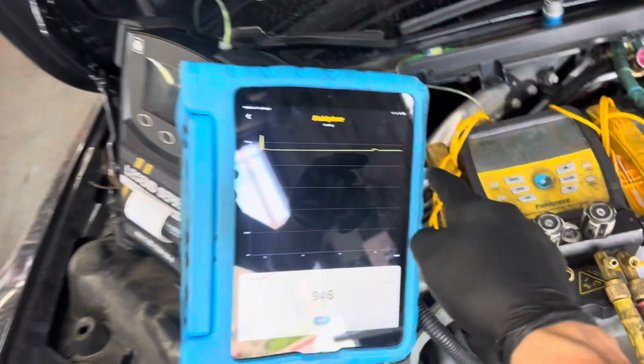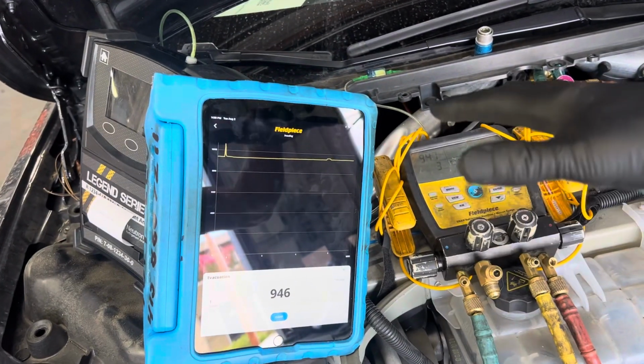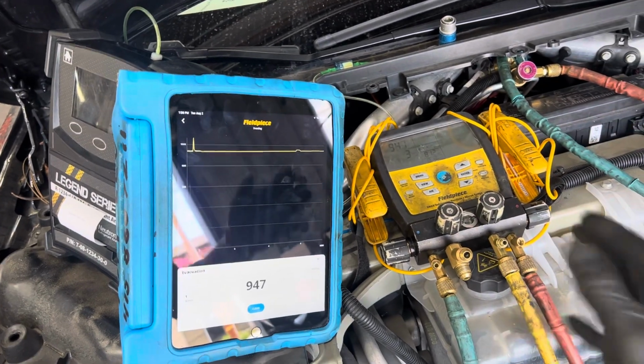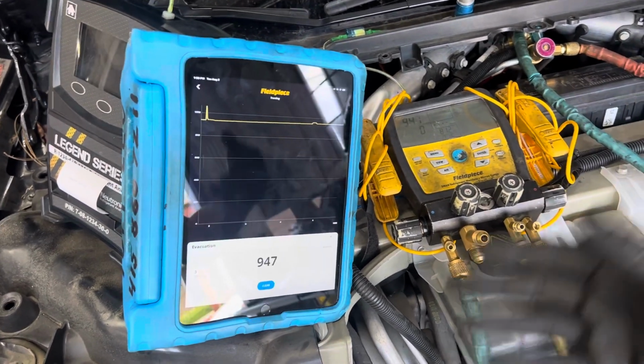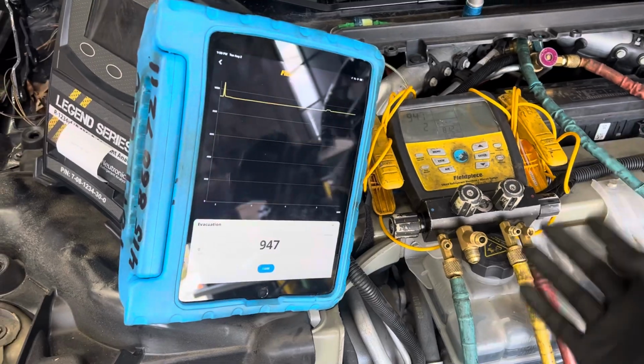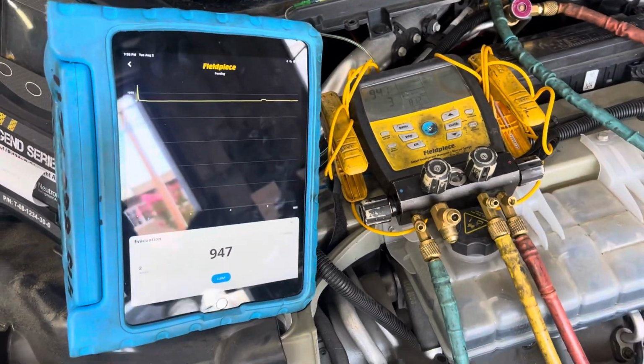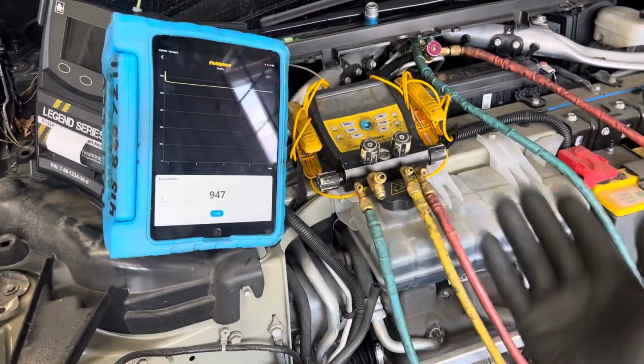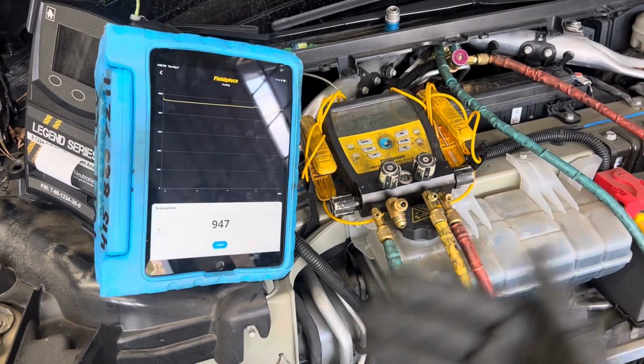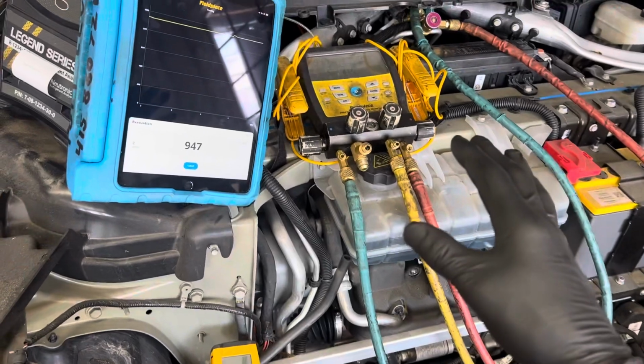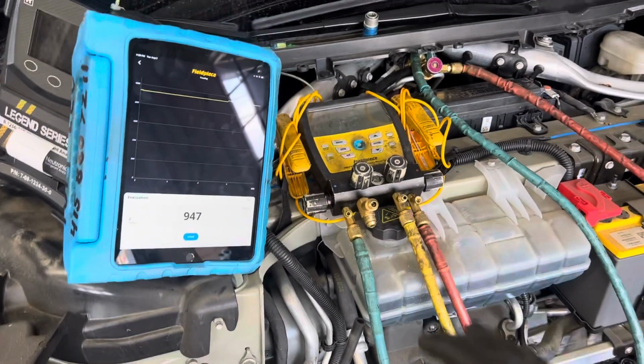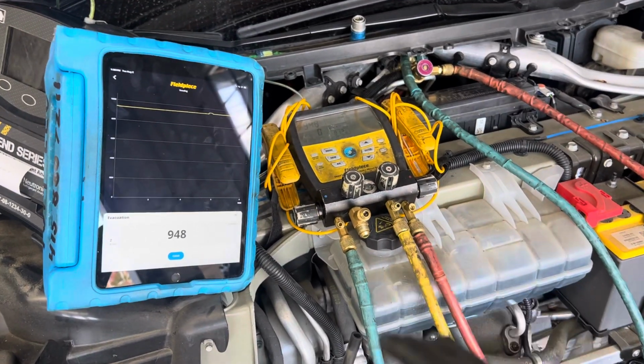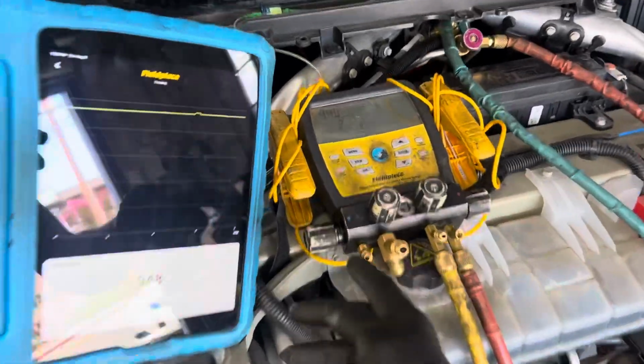I'm doing a standby test to see if there's a rise, if there's any refrigerant trapped in the system and it's going to boil off. That would be a waste of refrigerant, and that's refrigerant unnecessarily put into the atmosphere. So the EPA here in the United States, for those people outside of the United States who don't know, require you to pull down refrigerant to a negative 15 inches mercury vacuum. I go far and beyond that. I go all the way down, and I'm usually below 1,000 microns.